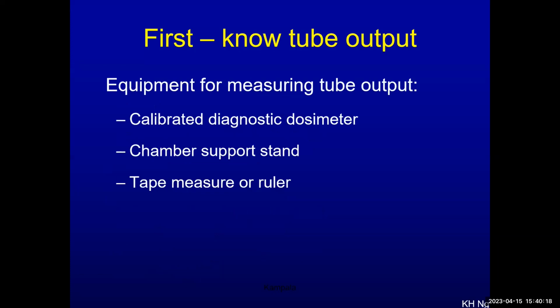The other one is just if you know the output, and that would be good, right? Unfortunately, most papers still use the roentgen as output, per mAs at 100 centimeter, so they need to convert that. Of course, we need to measure the output, which is quite standard for QC, with a calibrated dose meter, ruler and others as well.